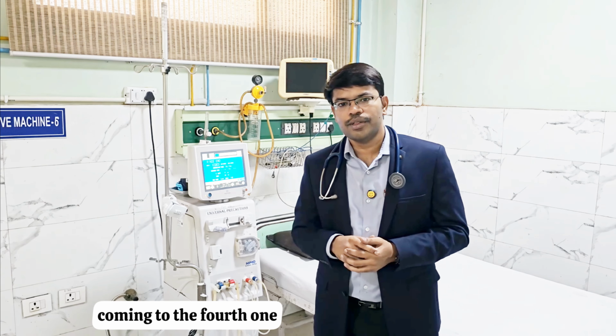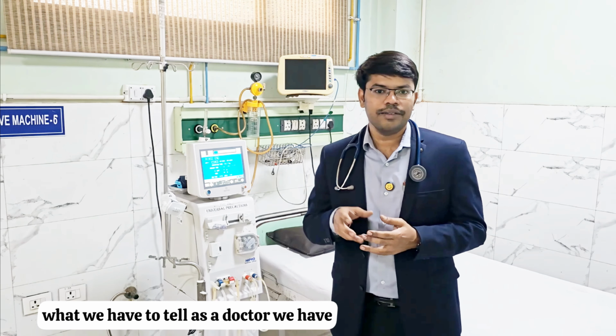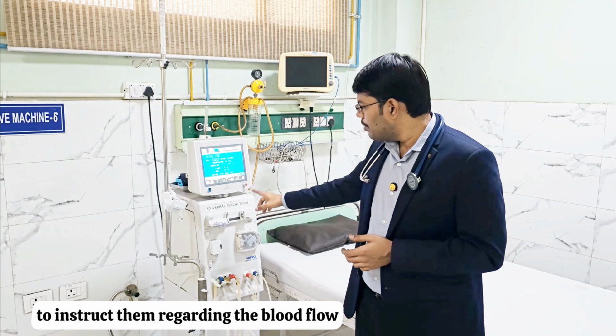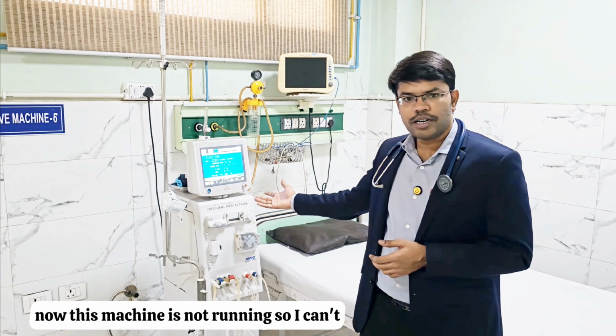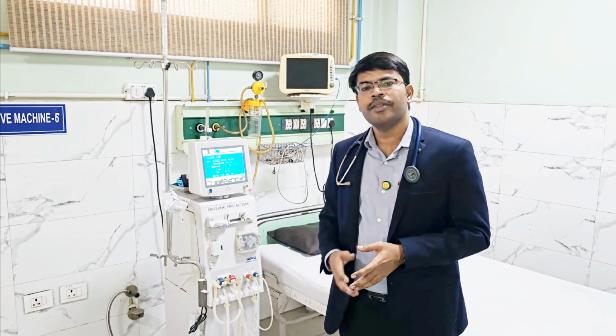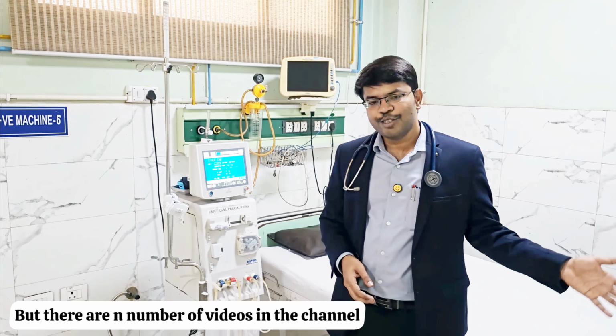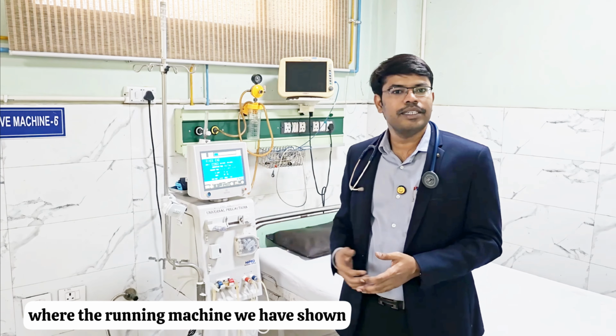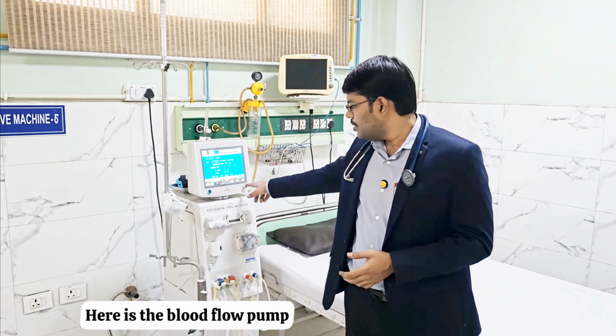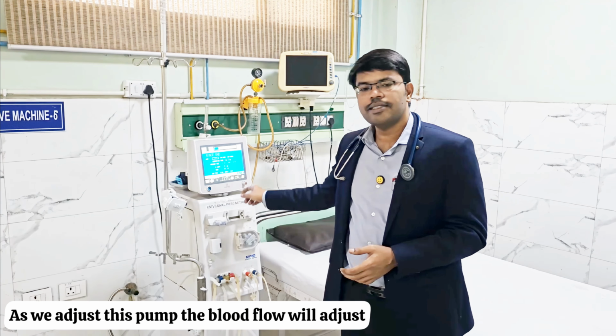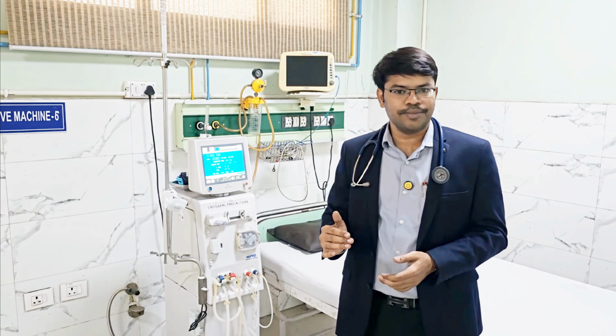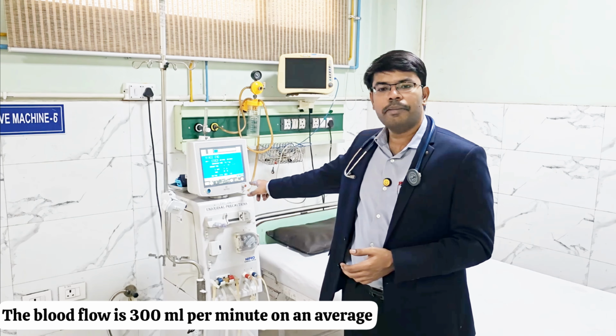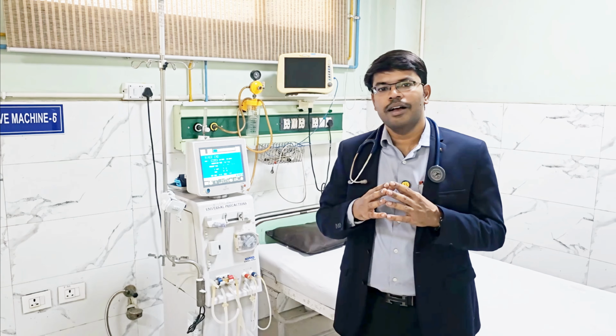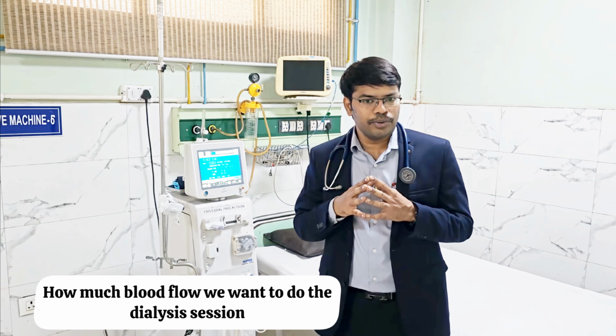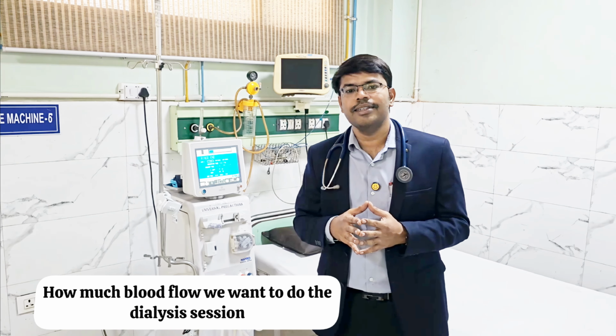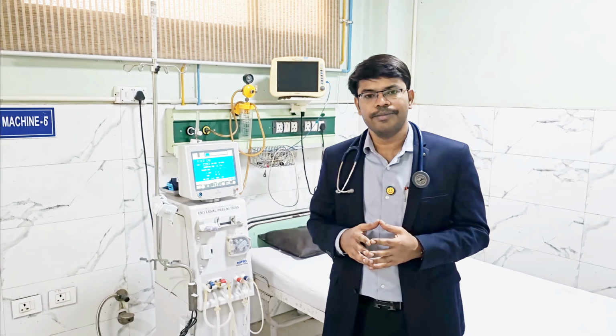Coming to the fourth one, what we have to tell as a doctor, we have to instruct them regarding the blood flow. Now this machine is not running, so I can't show you the demo, but there are n number of videos in the channel where we have shown the running machine, where here is the blood flow pump. As we adjust this pump, the blood flow will adjust. The blood flow is 300 ml per minute on an average. How much blood flow we want for the dialysis session has to be instructed.